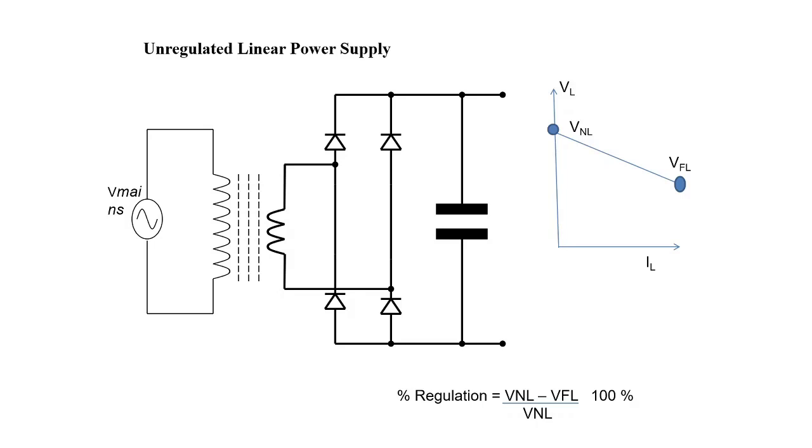Sometimes this figure is also calculated as V no load minus V full load divided by V full load. If it is calculated as V no load minus V full load divided by V no load, it is called as down regulation. If it is calculated as V no load minus V full load divided by V full load, then it is called as up regulation. Mostly down regulation is preferred which will have at the maximum 100% value.